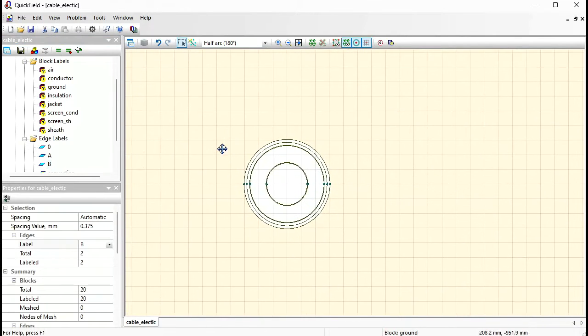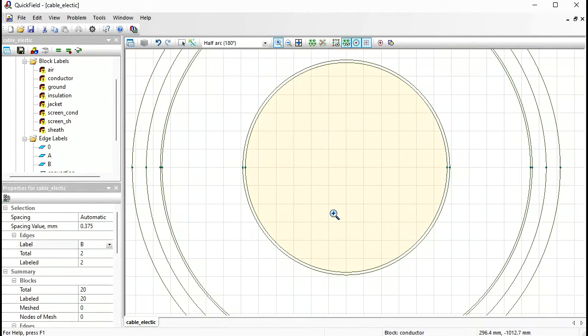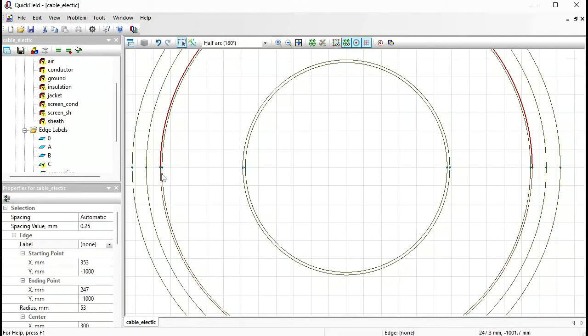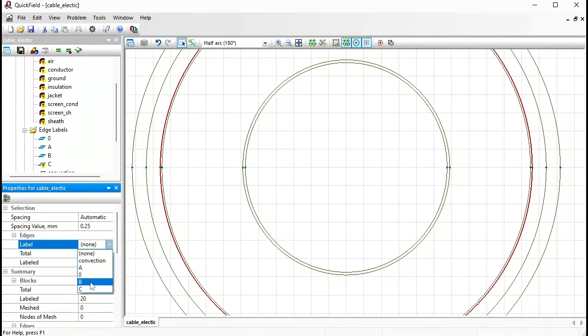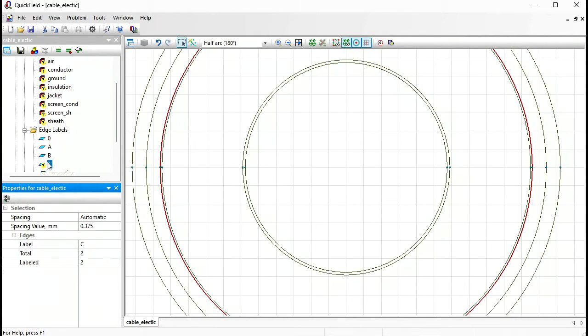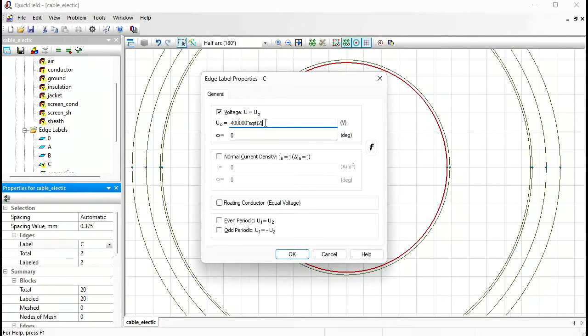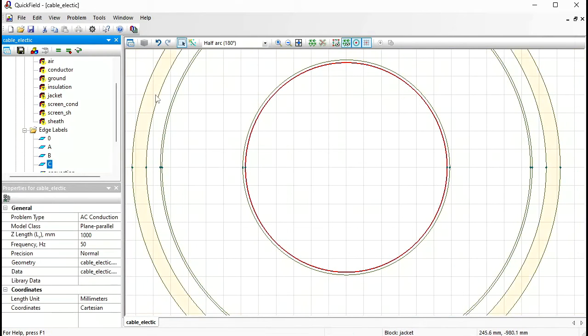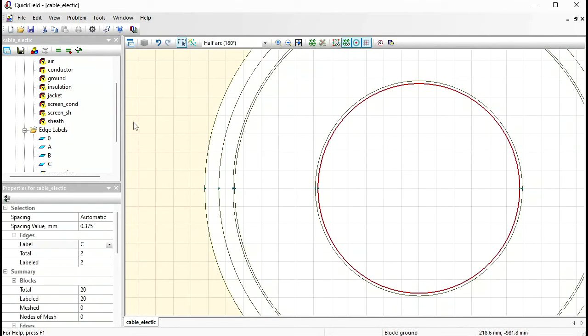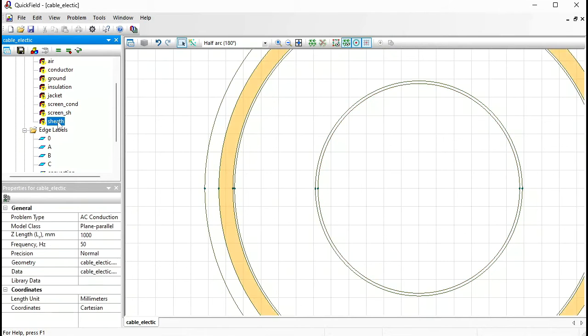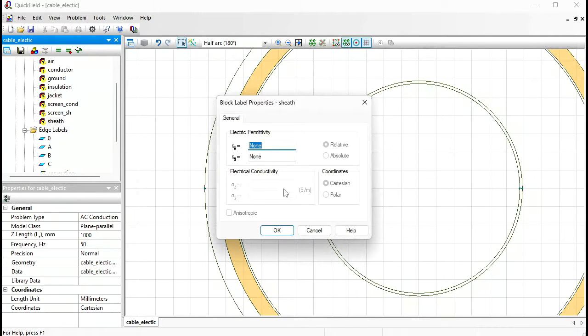Okay, let's proceed with the conductor phase C. Again, I assign label with conductor surface, phase C. I assign label to the sheath surface, 0. And for the conductor surface, I specify electric potential value. And the phase shift now is 240 degrees. Okay. As I said, there is no electric field inside conductor, so for the sheath, I don't specify any properties.